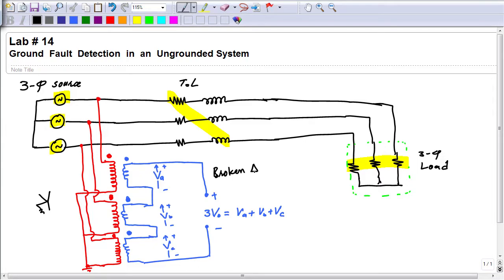In a perfectly balanced, healthy condition, the sum of these three voltages VA, VB, VC, which will appear between these two terminals of the broken delta, will be equal to 0. But in case of a line to ground fault, let's say a line to ground fault has occurred in this third phase, although there will be no current through this fault path because the system is ungrounded, we still want to detect this grounding.